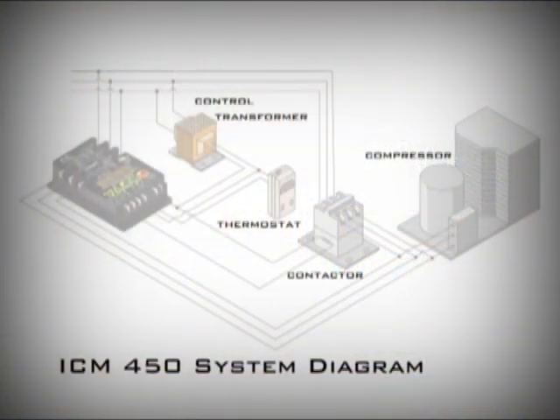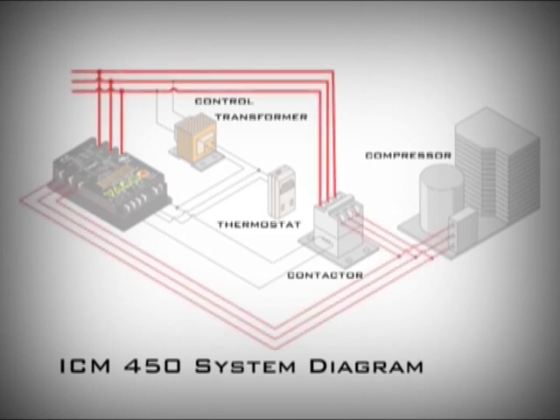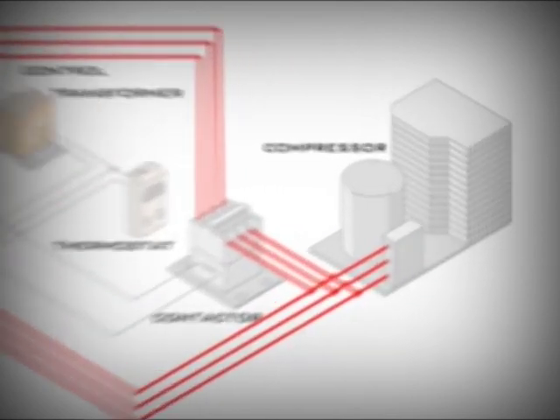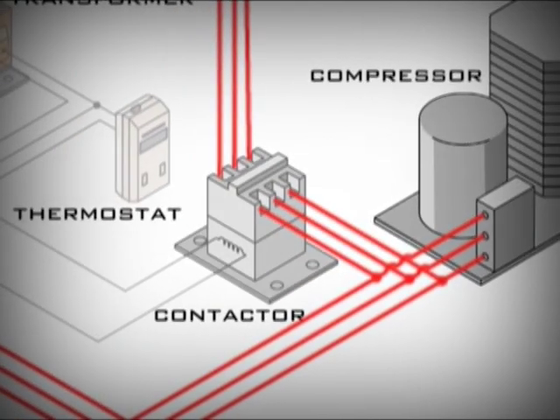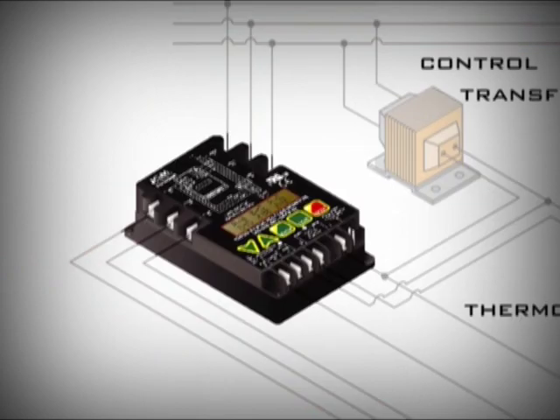With the ICM 450, your equipment is protected against power supply problems on both the line side and the load side. All power monitors check the incoming power, but most don't monitor the power at the compressor itself. So one of the most common causes of power supply problems — a malfunctioning contactor — gets completely overlooked. The ICM 450 provides compressors with total protection from power-related problems.